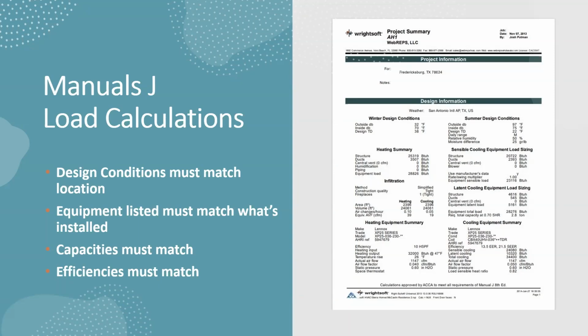My thing is, as they say, what's the top three? Well first, collect these manual J and S. Secondly, is it the correct one for the project being reviewed? Does it have the right address on it? Does it have the right weather data? This one shows it's being built in Fredericksburg, Texas, but they're using weather data from the closest international airport, which is San Antonio. If you get this one and you're in the Dallas area, that's incorrect - that's trying to use a different climate zone. It needs to be using your closest data.